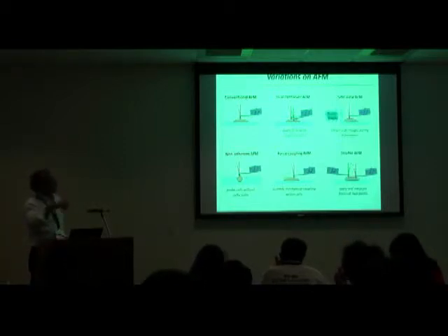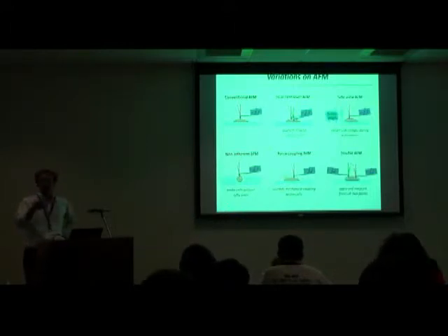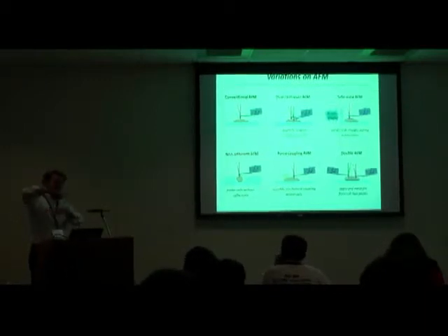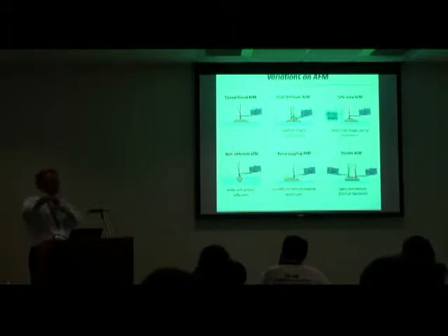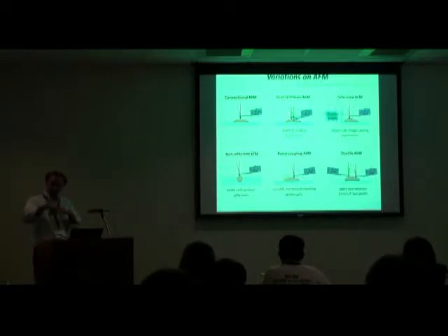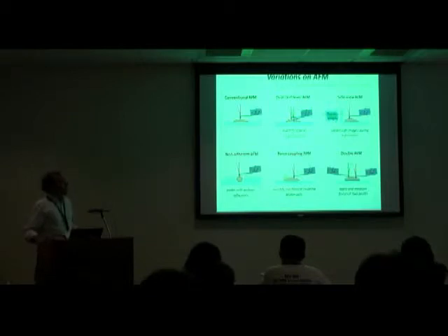The dual cantilever system uses two adjacent cantilevers to be able to normalize out for drift. Those of you who have worked with AFM know that drift is a real big pain. The cantilever base essentially moves relative to the substrate, and as a result, you don't really know where you are. You don't know what your reference point is for long timescale measurements. So to deal with that, we developed a system that uses one cantilever to figure out where you are, and a second cantilever to measure a sample.